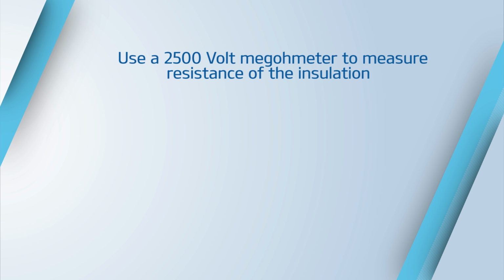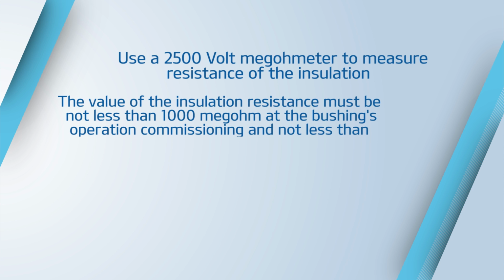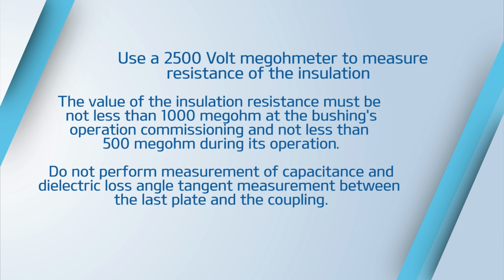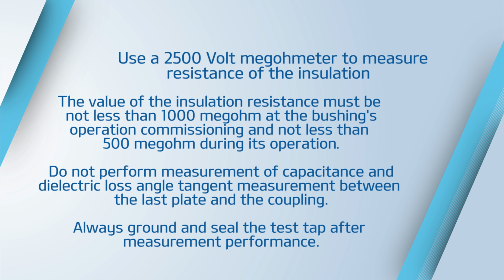Let's repeat the key steps. Use a 2500 volt megohmmeter to measure resistance of the insulation. The value of the insulation resistance must not be less than 1000 megohms at the bushing's operation commissioning and not less than 500 megohms during its operation. Do not perform measurement of capacitance and dielectric loss angle tangent measurement between the last plate and the coupling. Always ground and seal the test tap after measurement performance.